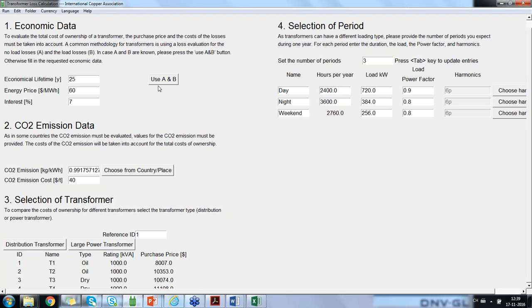Related to your question, did we take into account voltage harmonics or current harmonics? We only took into account the harmonics which are caused by loading, so in this case only the current harmonics. The voltage harmonics, that's something which you also see within transformers, but that's because the transformer itself is a non-linear load due to the core. Voltage harmonics have not been taken into account in this transformer tool. That could perhaps be an expansion later on, but then you already get a more sophisticated tool. And from my point of view, the voltage harmonic content will not have such a high impact on the total losses compared to the harmonics in loading that you have.